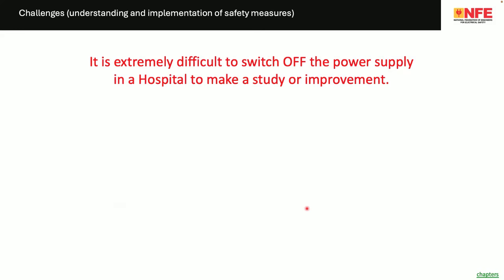Coming to the conclusion of the challenges, it is extremely difficult to switch off the power supply in a hospital to make a study or improvement. Imagine there are so many hospitals where we make the study, we make the recommendation, but implementing the recommendation is almost an impossible task because you are unable to switch off the supply. For example, once in 5 years, insulation resistance test is a mandatory requirement. And if you do insulation resistance test, not on the equipment, but on the installation, that means the wires, the cables, the switchgears, the protective devices, the transformers, the DGs, if the insulation resistance test is carried out properly, a lot of accidents can be avoided.